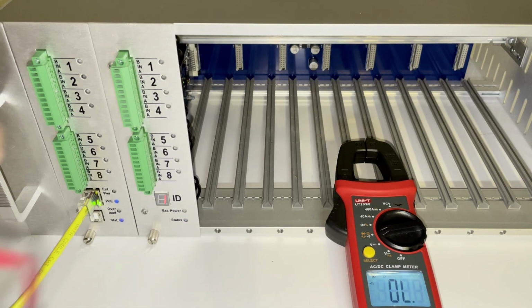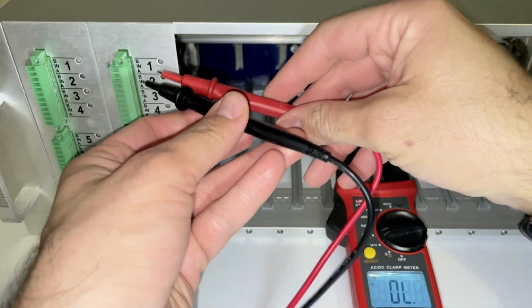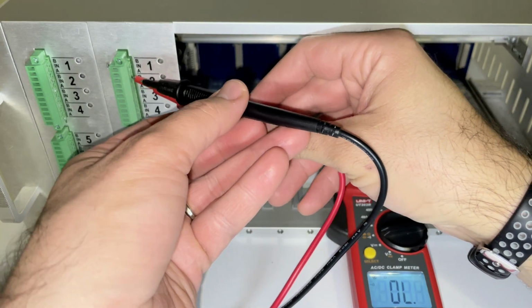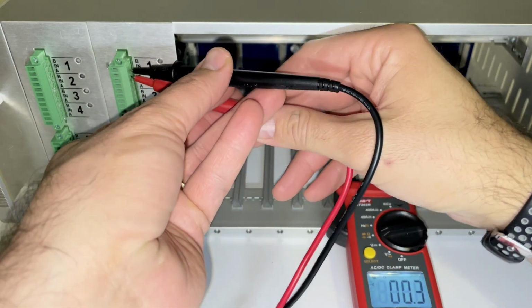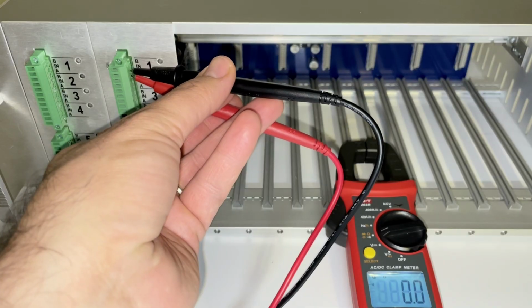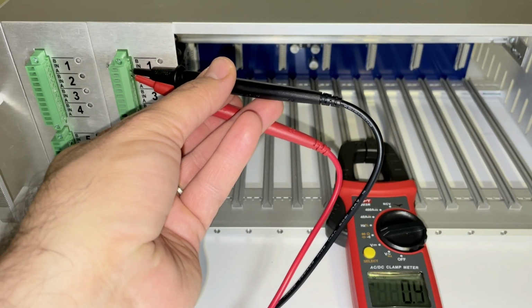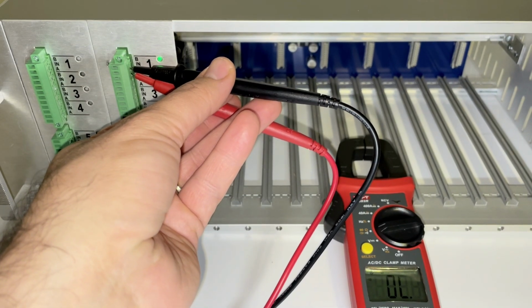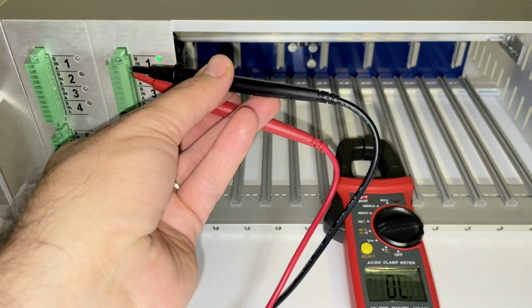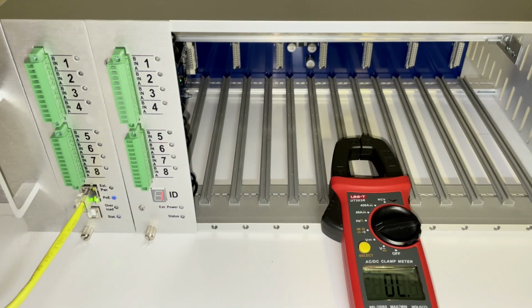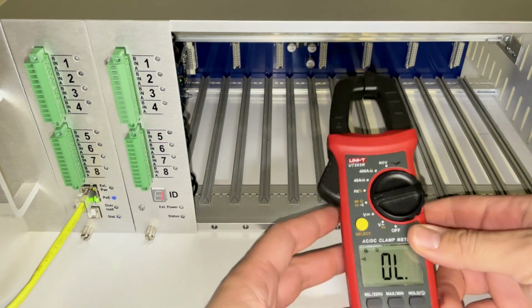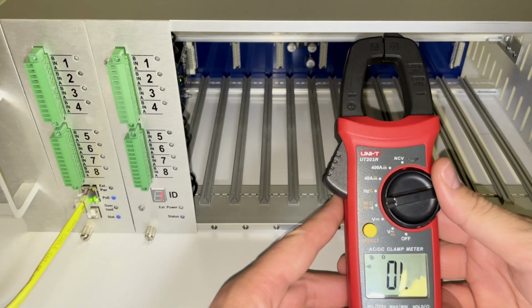Next, test the normally closed contact by placing the probes on the common and normally closed terminals. A continuous beep should be heard while the probes are in place. Once the system is triggered, the beep will stop and remain silent for as long as the system stays activated. As an alternative troubleshooting method, the dry relay can be tested using the multimeter's resistance measurement mode.